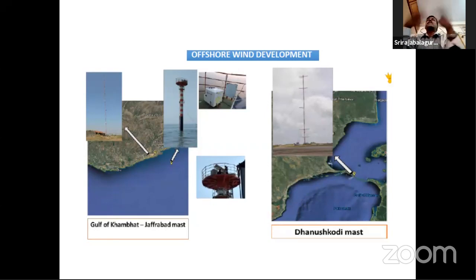It's a farm, so you have plenty of wind turbine generators around, and every time we cannot watch them. So it should be provided with LVRT. That means when it is running at 100% or 80% and a sudden dip occurs, it will withstand it without any grid separation and maintain stability, up to 15%. So now all the wind turbine generators are LVRT and pitch regulated machines. And why I'm talking about this is offshore. We have started from 22 kilowatt, 55, and now 2.5 megawatt plus. This is the onshore study.